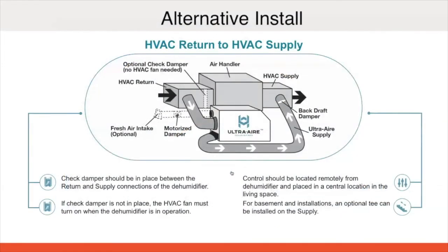So an alternative install is the HVAC return to the HVAC supply, because a lot of times in retrofit especially, it's hard to pull that dedicated return. So here we're going to have to either use a check damper in that return before it gets into the air handler, or we're going to have to run the fan on that air handler to move that air through.